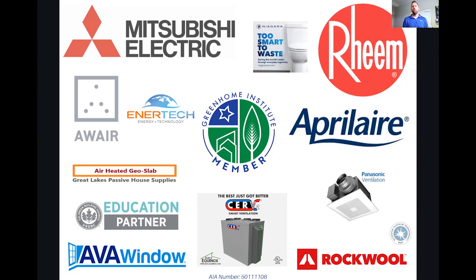I saw a lot of ERVs going in, and it blew my mind. I started asking, why are we using ERVs? It was, if we continue to use a bathroom fan as an exhaust, the problem wasn't that the bathroom fan didn't work. It was that when you have that much moisture, the hot, humid air is actually migrating through that duct trying to make its way into the home toward the cooler, drier air. It was condensing inside that pipe, condensing on the grill, and it started to deteriorate the drywall right around the bathroom fan.